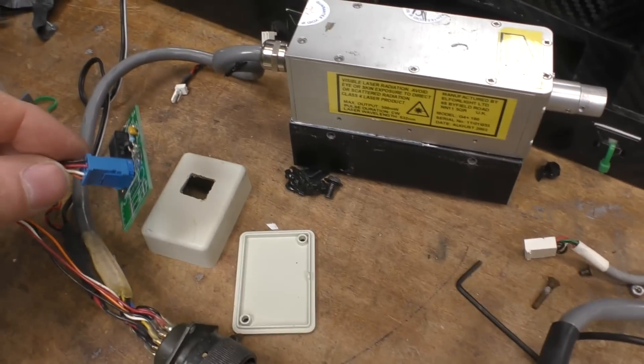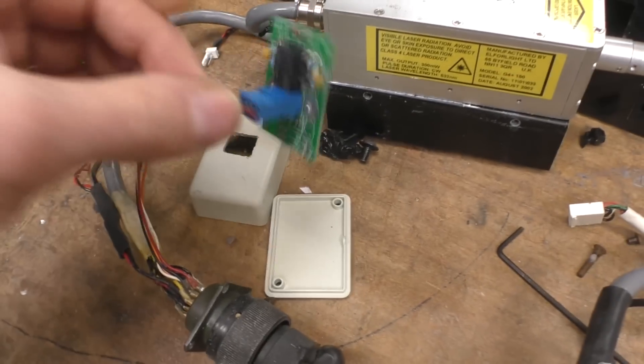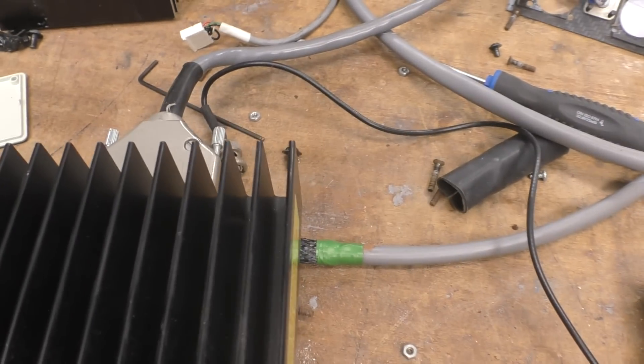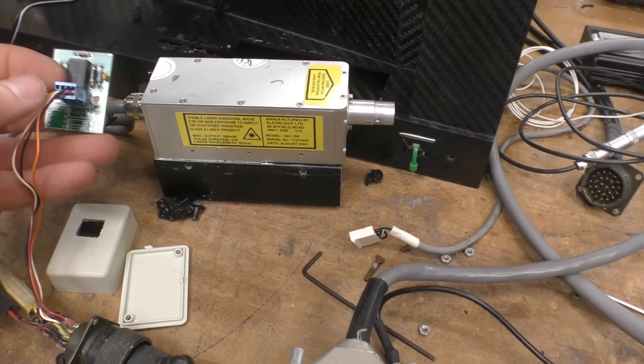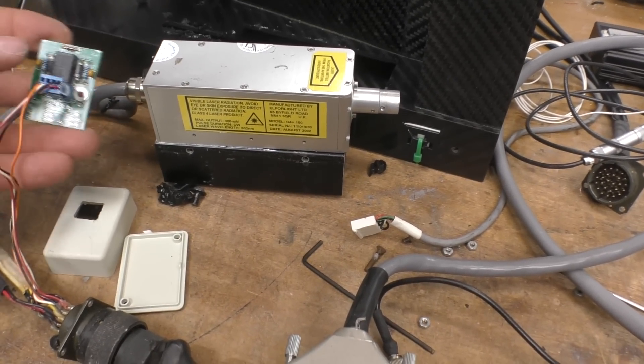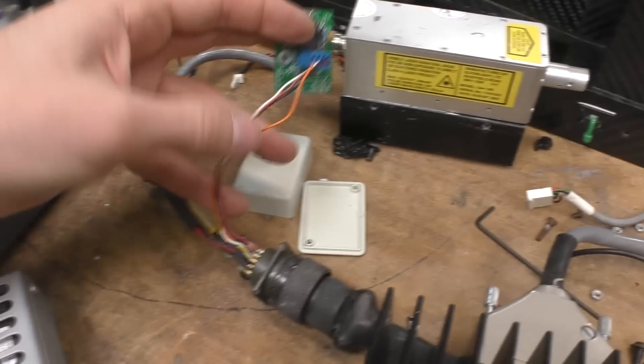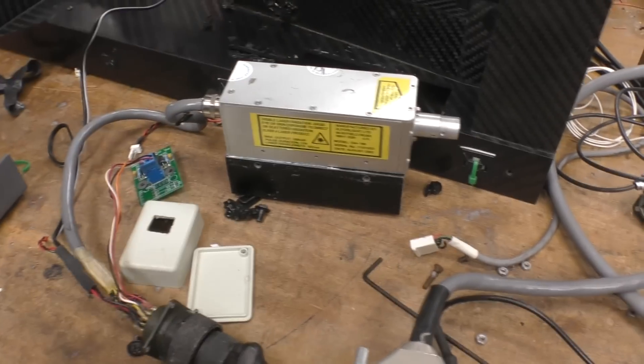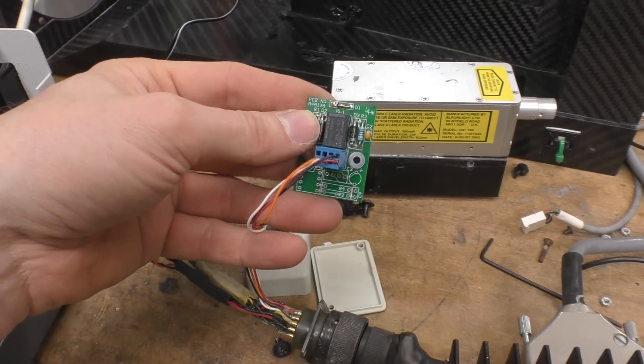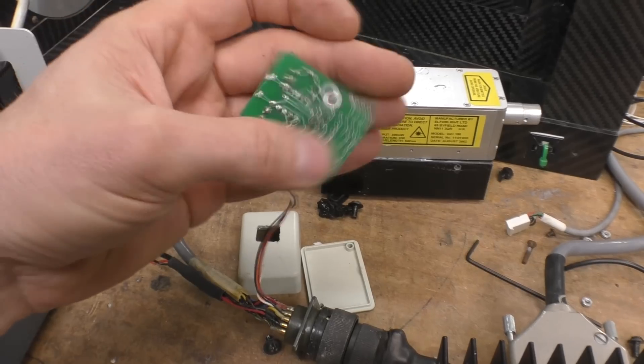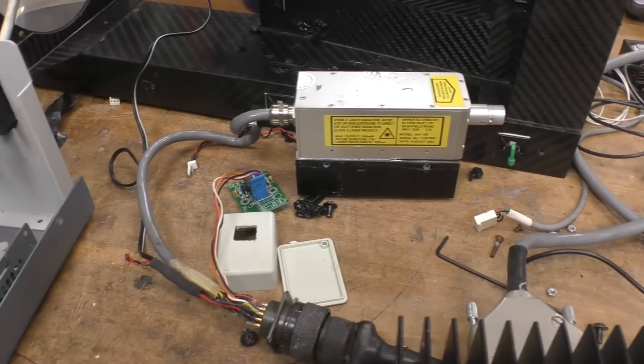When I was taking it apart I found this little box inside with a relay board. I think what this is is for protection of the laser diode, because the laser driver has an external connector to connect to the laser. Laser diodes are very sensitive to transients and ESD. I think what this is doing is probably shorting out the laser diode until it gets the signal from the controller to say it's okay, we're all connected. It isolates the fragile laser diode from anything that could happen on these external connectors. This is manufactured by the laser manufacturer, so this is clearly a standard accessory they provide for this application where you remote mount the driver from the laser head.